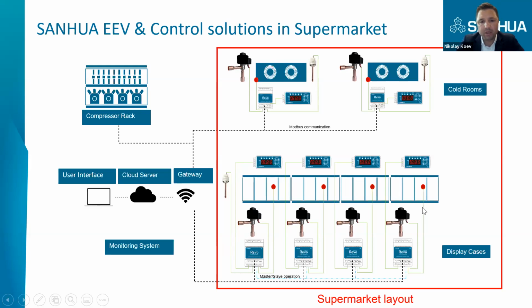If we have several cabinets, then we can use the master-slave option. So the first controller can be master and the rest can be slaves. We can connect up to 9 slaves, so they can share the information received by the pressure sensor on the master controller. So it is quite a simple solution, but using this solution, you can achieve the maximum energy efficiency, especially compared to thermostatic expansion valves.